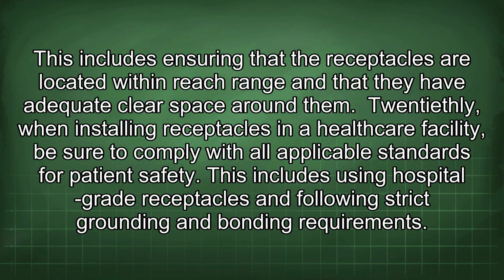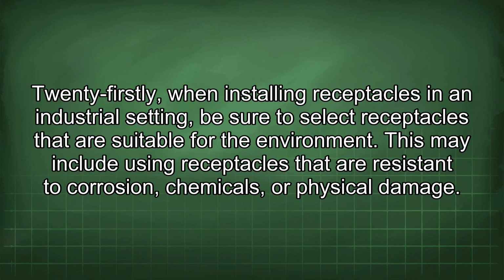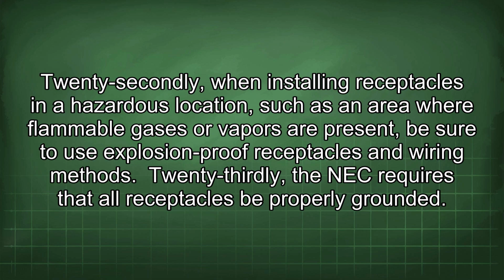20thly, when installing receptacles in a healthcare facility, be sure to comply with all applicable standards for patient safety. This includes using hospital-grade receptacles and following strict grounding and bonding requirements. 21stly, when installing receptacles in an industrial setting, be sure to select receptacles that are suitable for the environment. This may include using receptacles that are resistant to corrosion, chemicals, or physical damage. 22ndly, when installing receptacles in a hazardous location such as an area where flammable gases or vapors are present, be sure to use explosion-proof receptacles and wiring methods.